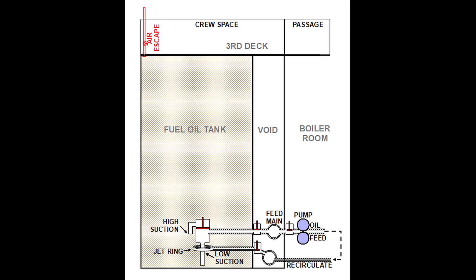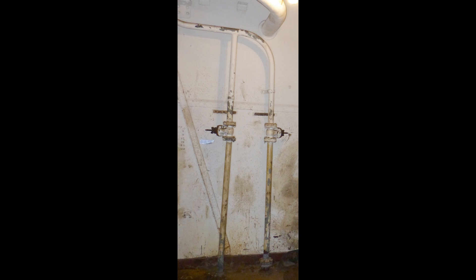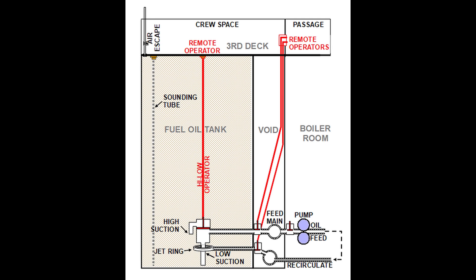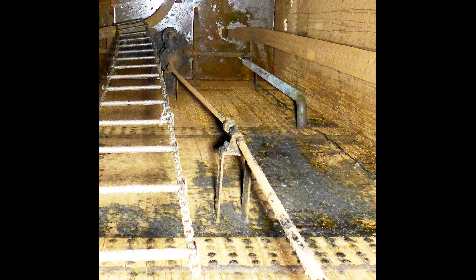If we go back to the tank, we can see a somewhat mysterious disc mounted on the high-low valve. A little digging through old drawings identifies it as a jet ring, whose important function will be discussed a little later. Fuel tanks also have to breathe as fuel is pumped in or out of them, so each has an air escape line that pipes from the tank top to outside of the ship so that toxic fumes aren't released inside. Each also has a stop valve that, when shut along with fuel feed and recirculate stop valves, will allow the tank to be pressurized and tested for leaks. We can also see a sounding tube. While the fuel king and his crew were able to keep track of fuel levels with reasonable accuracy, it was occasionally necessary to perform a sounding with a lead line dropped into the tank or down a tube extending to the bottom. They also needed a way to quickly and cleanly open and close all valves from a convenient location — not by climbing down a chain ladder to the bottom of a void or swimming to the bottom of a 25-foot deep oil tank.